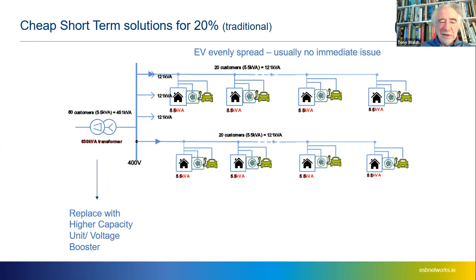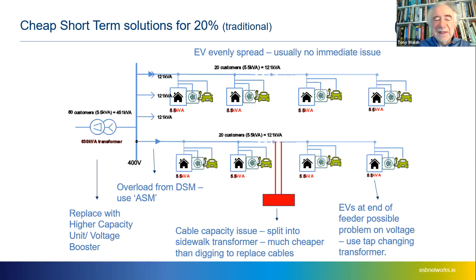If the cable in the middle of the network of an existing housing estate is overloaded, our proposed solution is to put in a sidewalk transformer so that we inject capacity into the cables rather than try and dig up the cables and put in bigger cables. If we have a problem at the end of the cable where the voltage drop is too high, well, then we'll make sure that the transformer we put into the substation is a tap changing transformer that can give out a higher voltage. And if we have demand side management facilities so that the grid operator can match load to wind, for instance, and that might overload the network, ASM, Advanced System Management, will make sure that this is controlled so it doesn't become a problem.